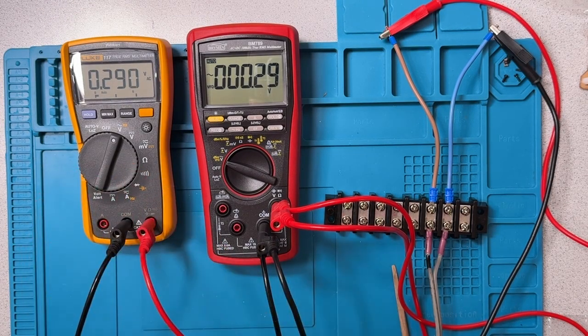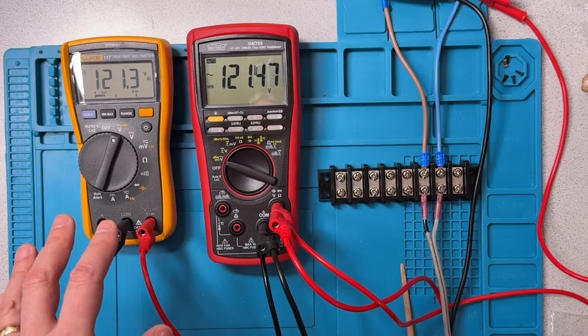We're set up for AC volts. The power's off right now. They're both showing about the same level of ghost voltage. If I turn the power on, they're both showing 121 volts. The Brymen is a touch higher there, about 1/10 of a volt higher from what we can tell. And the thing to look at is how long does it take for the reading to click in here. So the performance of the Fluke and the Brymen seem to be about equivalent in terms of settling in to the current AC voltage. Now with the power on, let's look at the frequency.